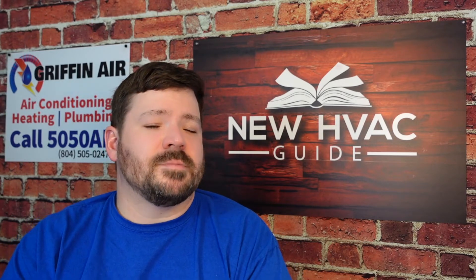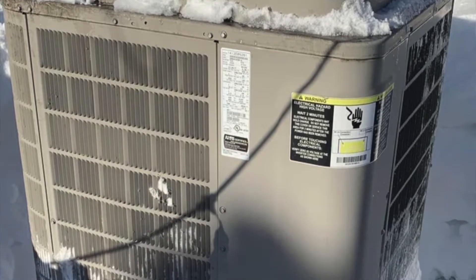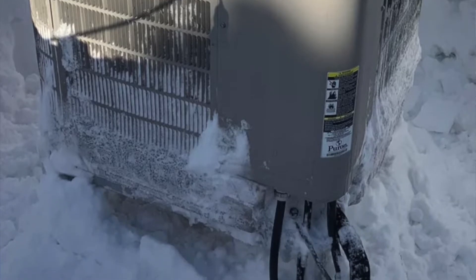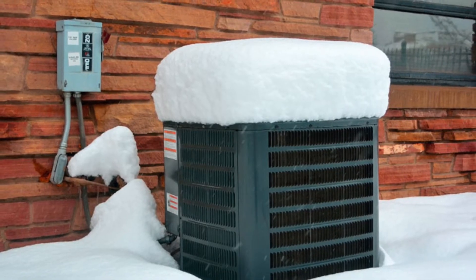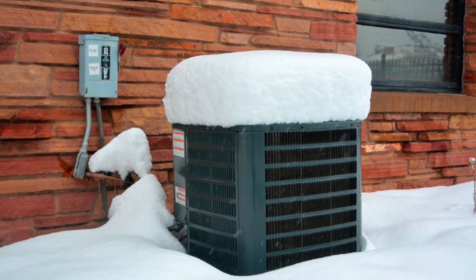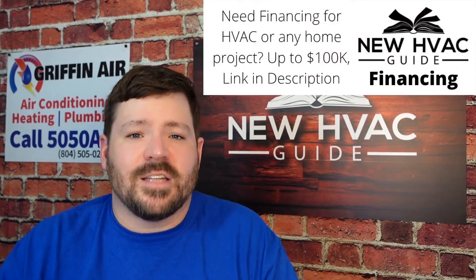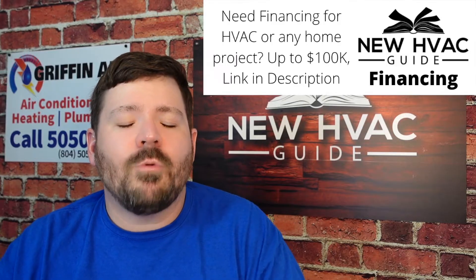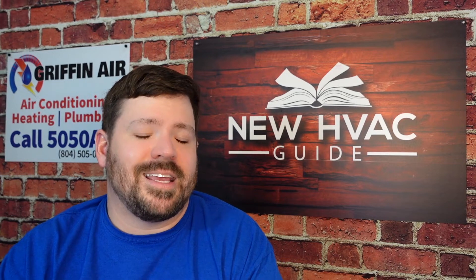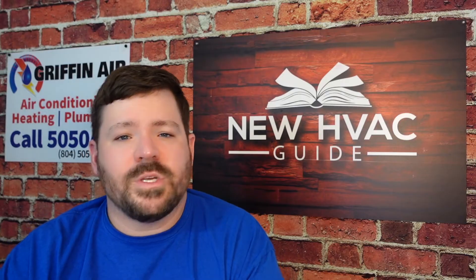Most of these systems historically did not turn off when the auxiliary heat turns on. I think there is an argument to be made that if it gets so cold outside that the heat pump is basically rendered useless — that it's just running and not actually providing any type of heat rise across that coil — then it could be argued that the system should turn off just based on efficiency. It's not doing anything anyway, so why pay for that extra energy? In most cases it's not as much energy as the heat strips, but you could make the argument.